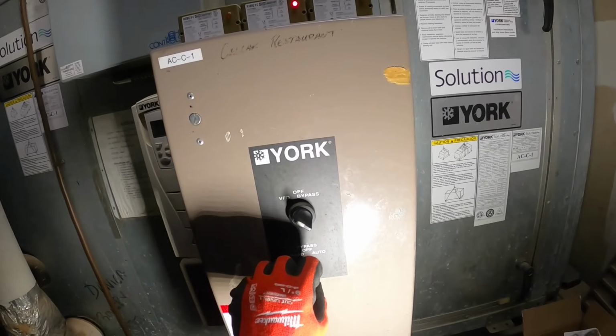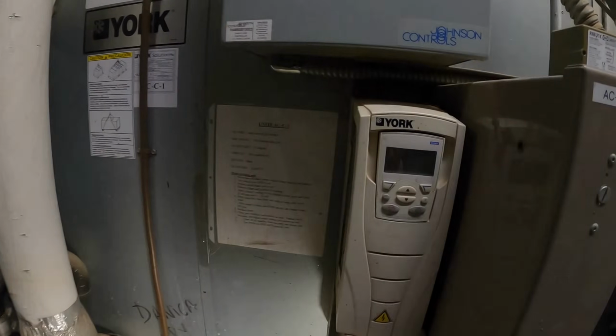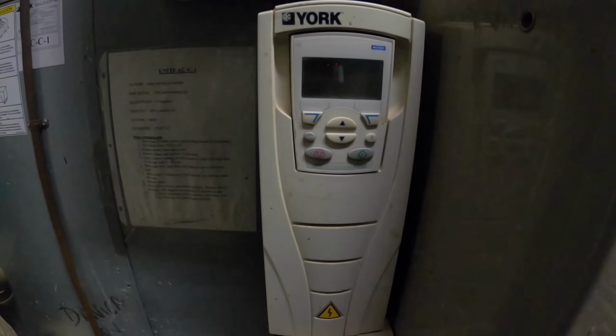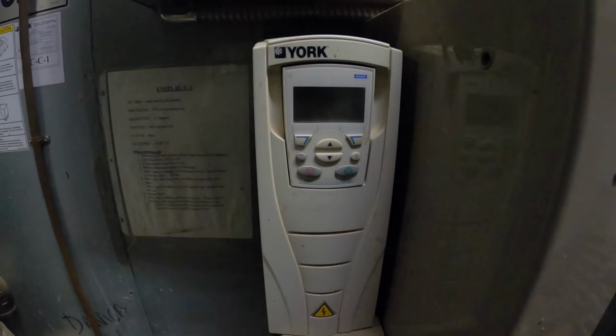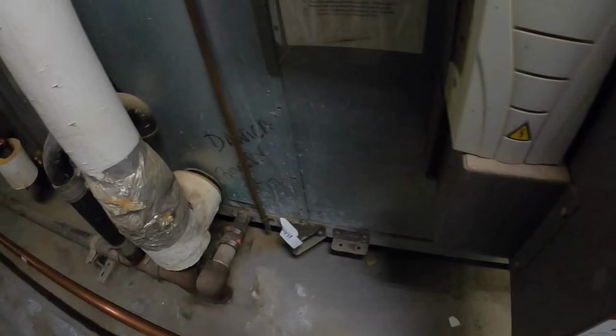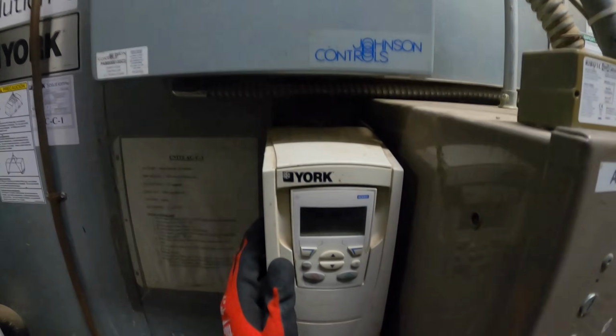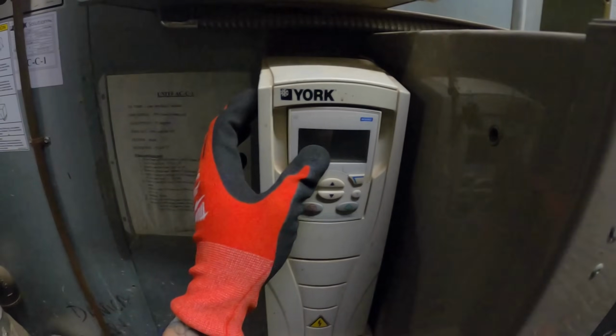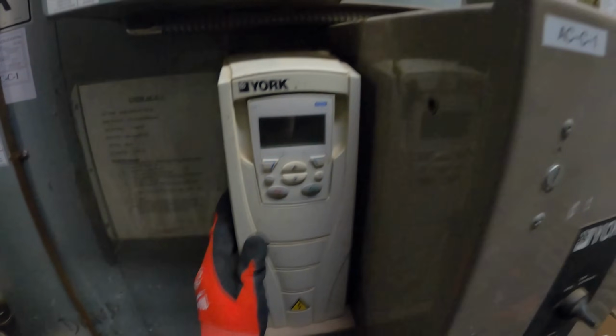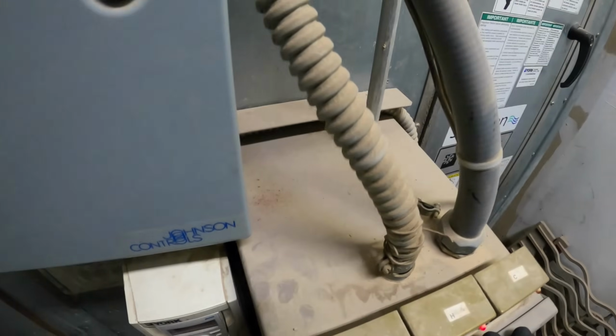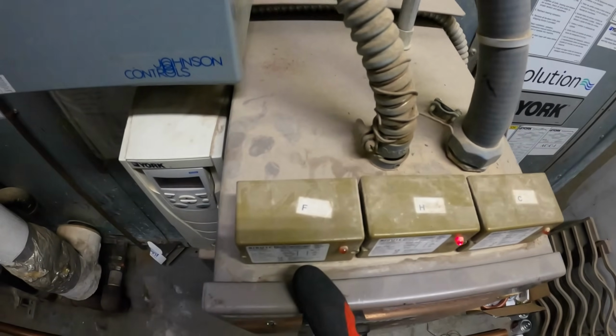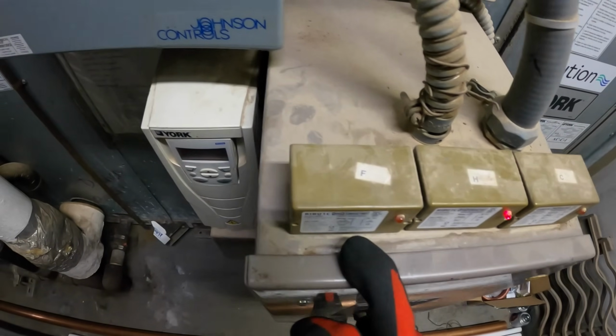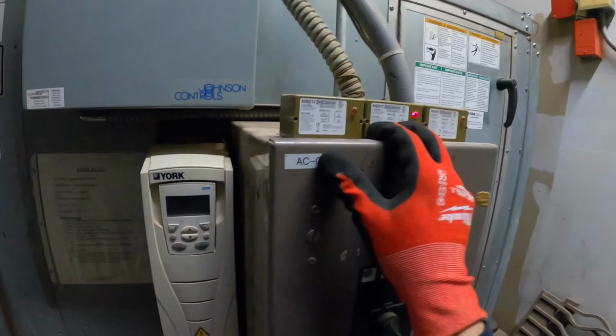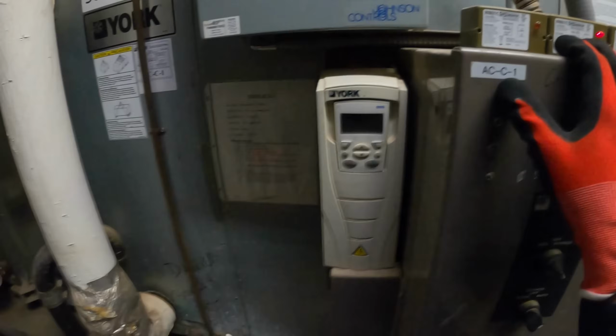Let's see if I put it on VFD and auto. Does anything come on this VFD? Does this thing light up or what? I think that should have automatically lit up. So if you're calling for heating, the fan should be on too, because we want heating. You're not going to get any heat in that case.